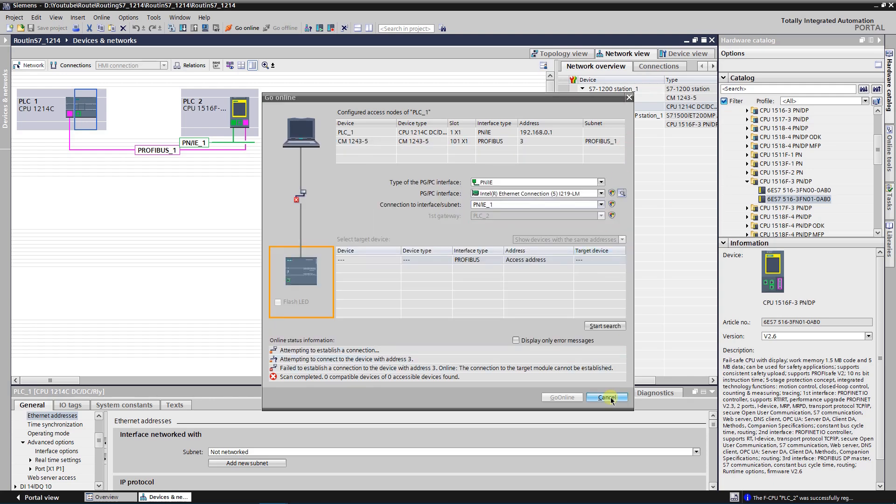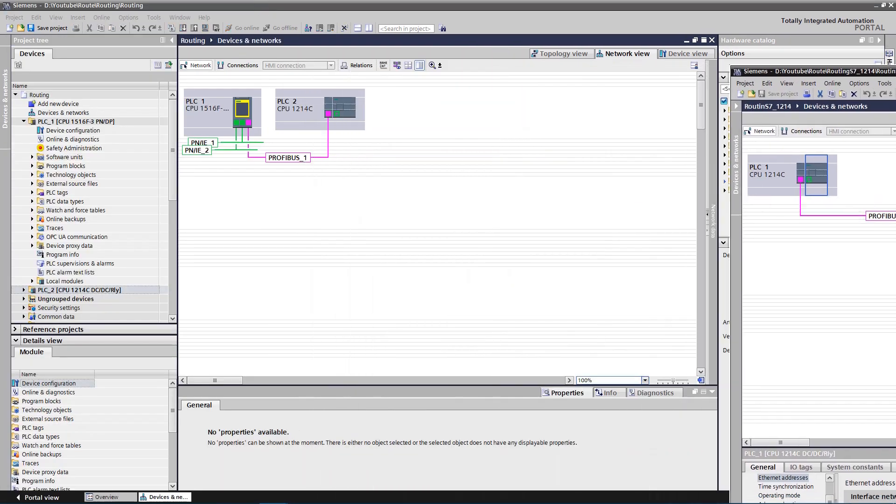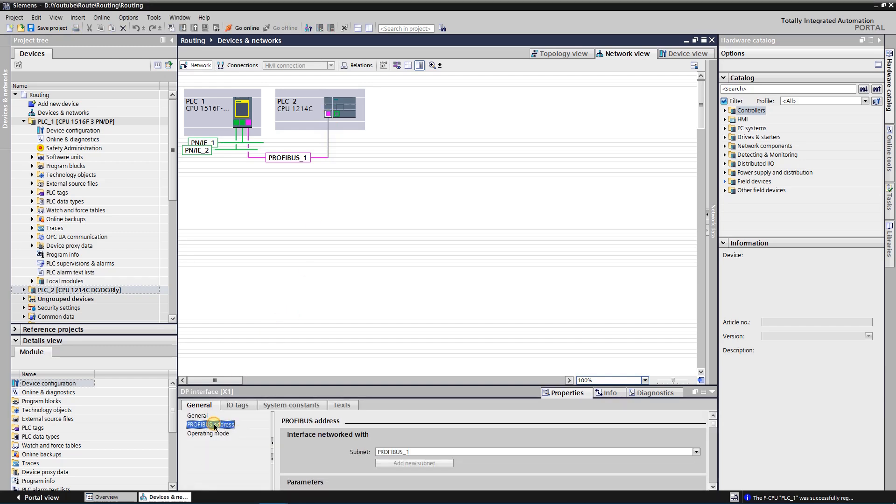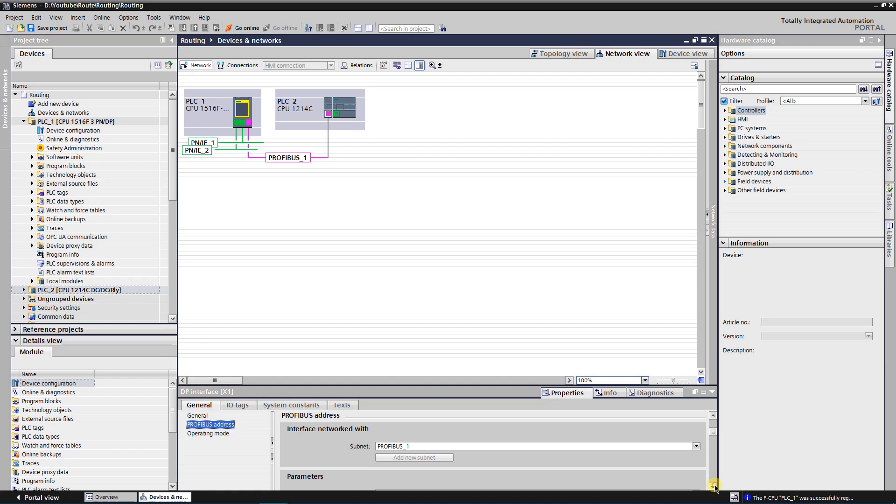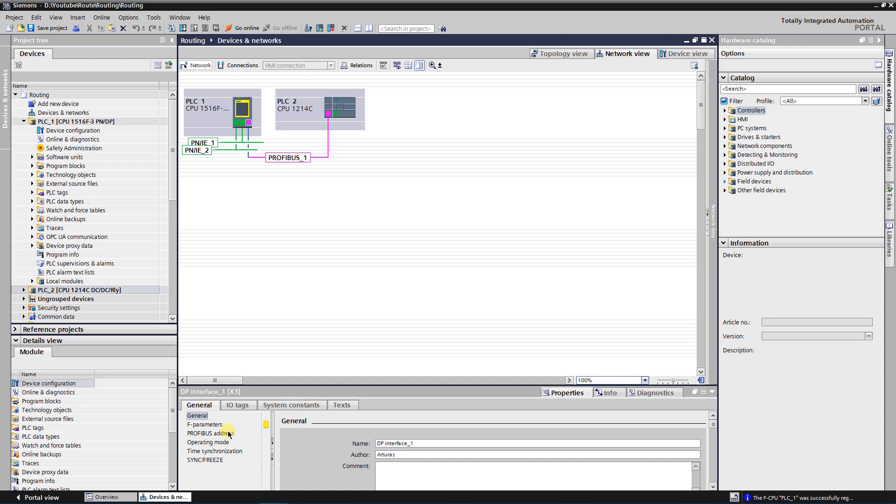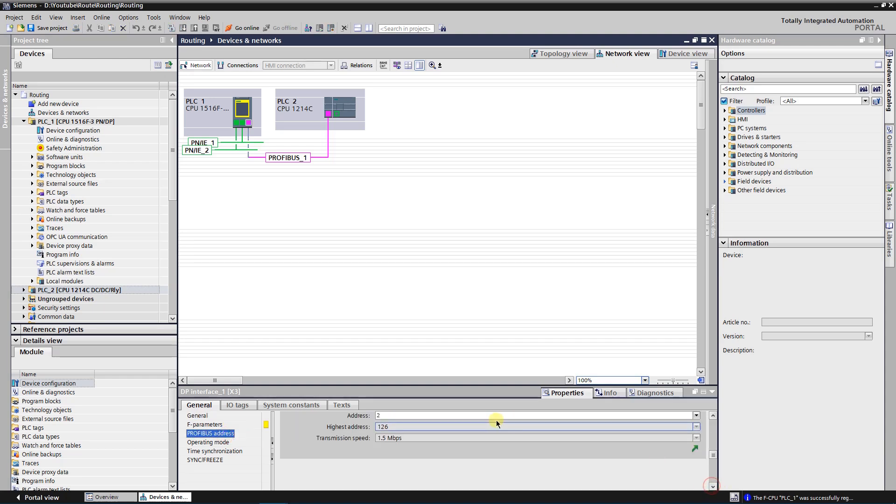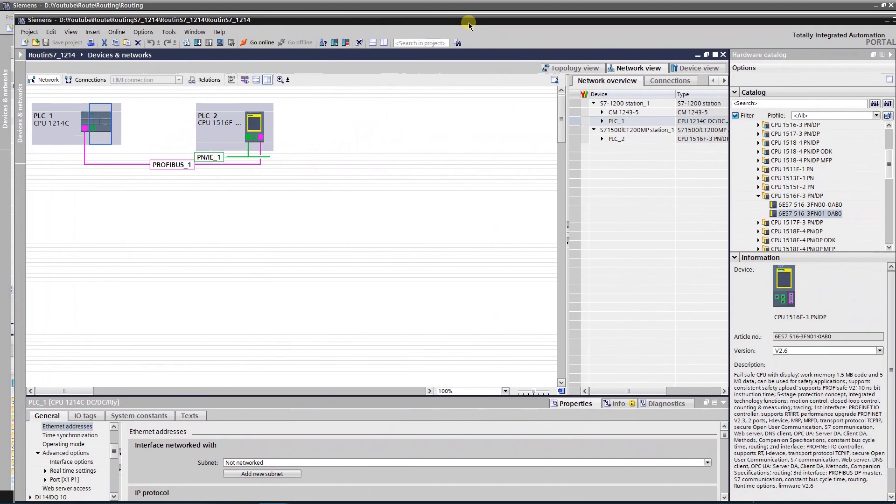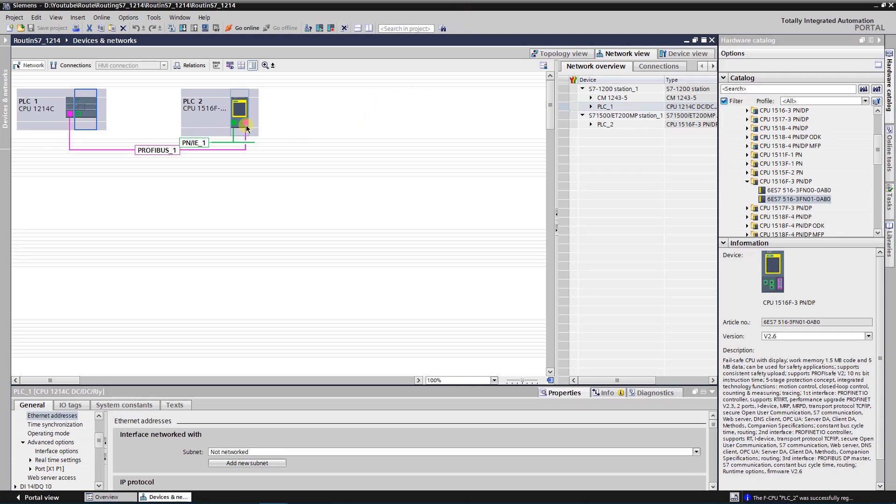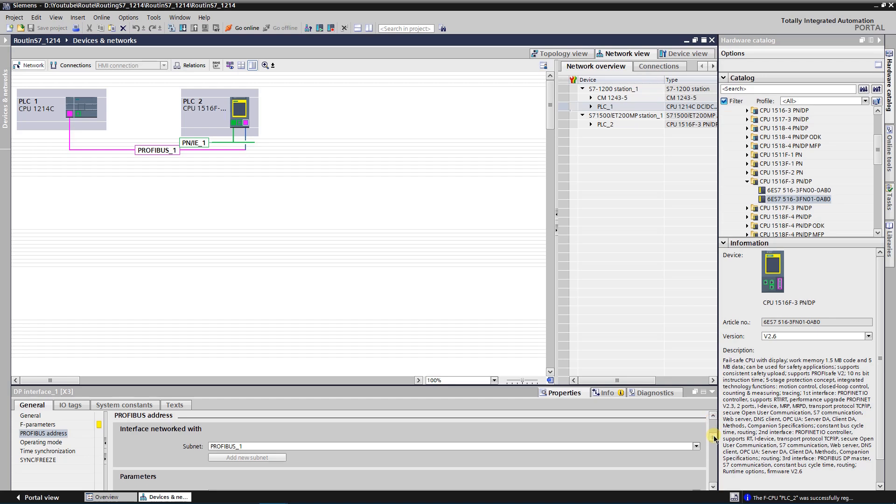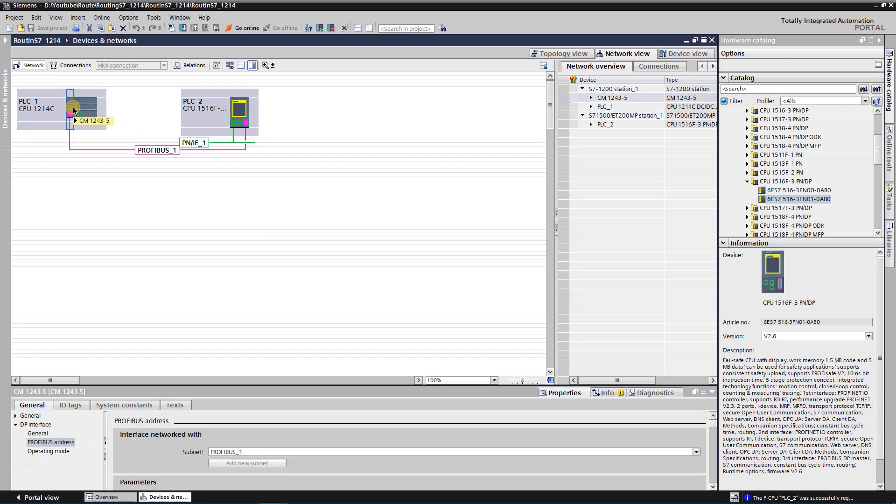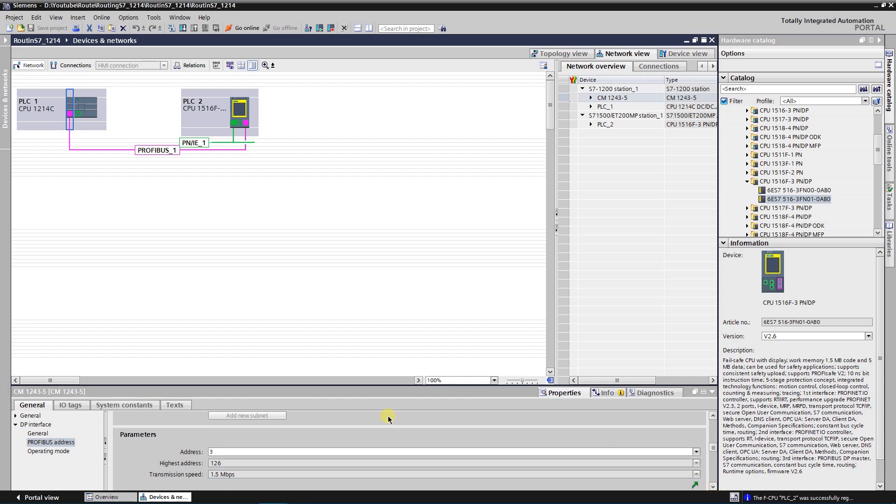First of all let's switch to another project. What do we have here? CPU 1214C has PROFIBUS address 3. CPU 1516 has a PROFIBUS address 2. Let's make sure that it is the same in separate project. In my case PROFIBUS addresses matches, if not, you need to change them. Now we need to compare S7 subnet IDs of PROFIBUS subnet.